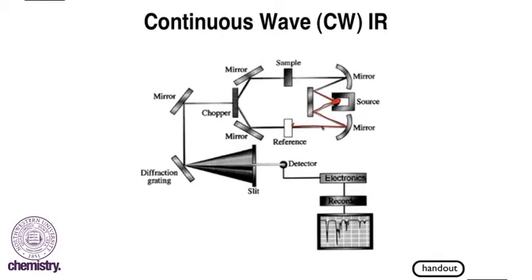We pass half of our IR light beam through a reference sample, which is basically just an empty chamber that will contain gases present in the room. The other half of the IR beam we pass through our sample chamber, which contains the material we're trying to analyze.